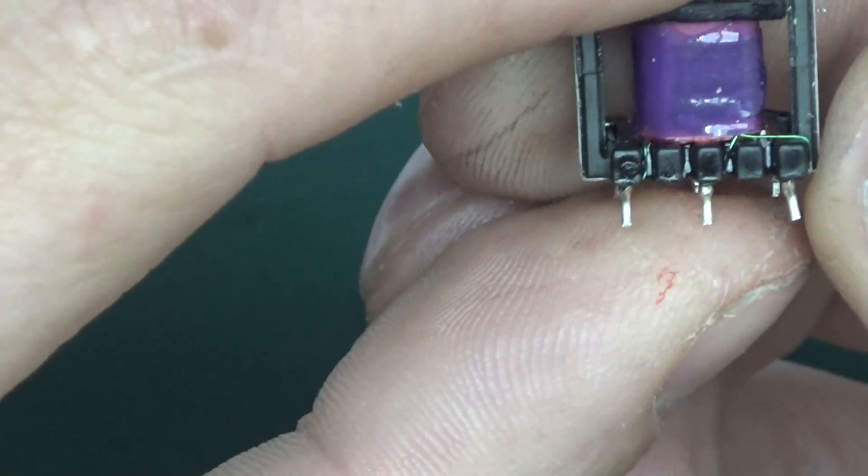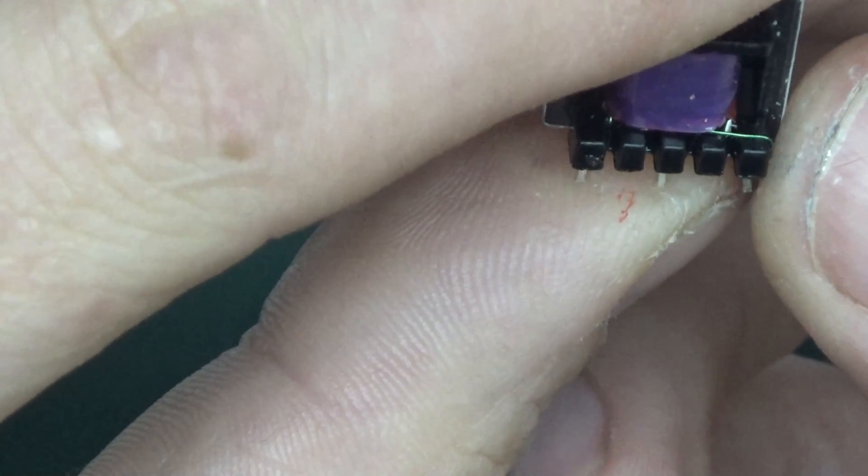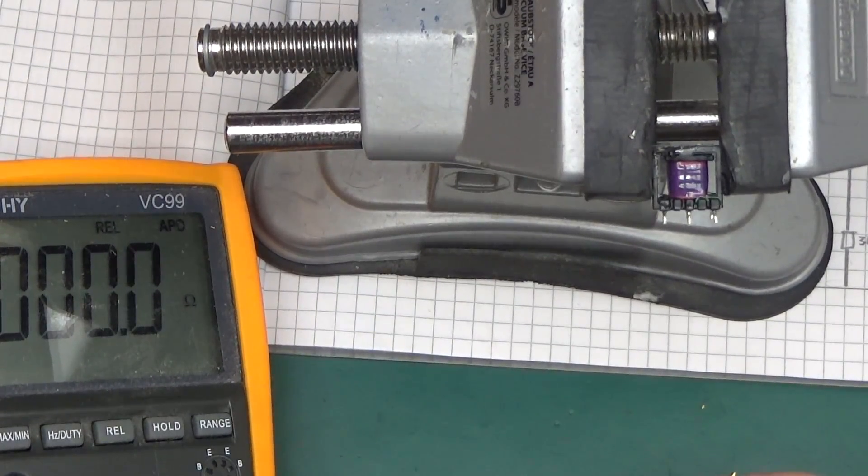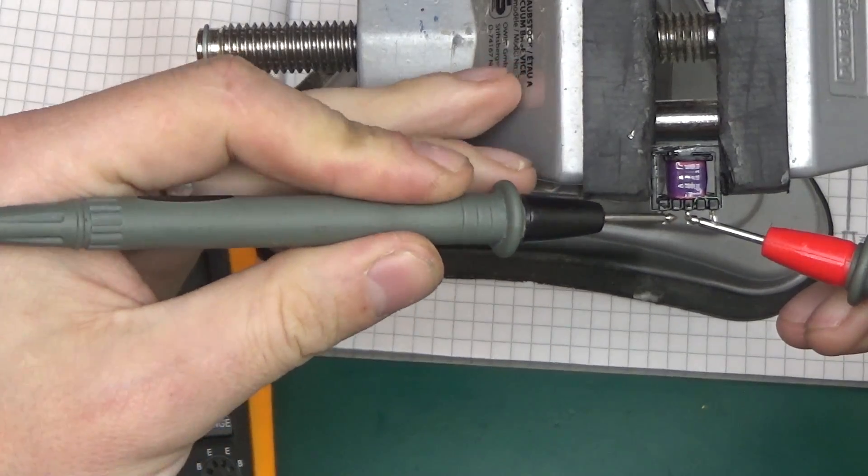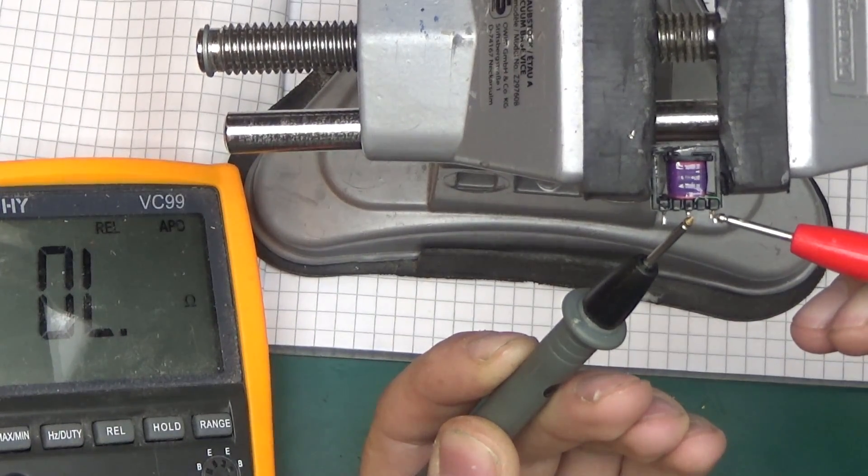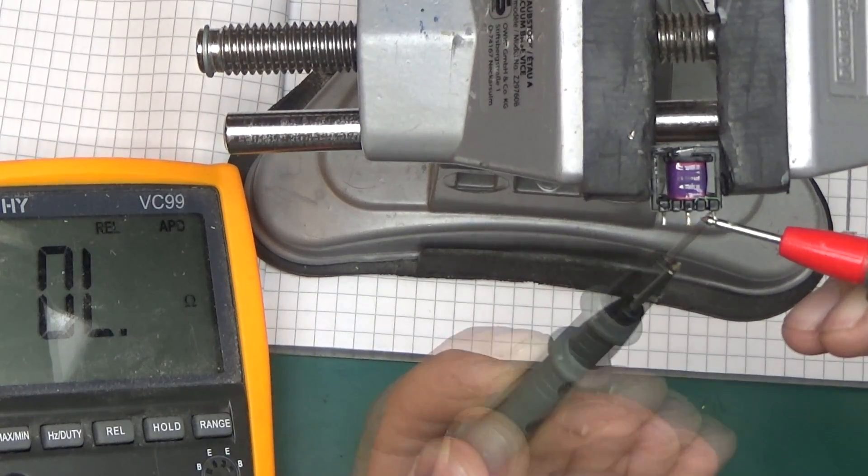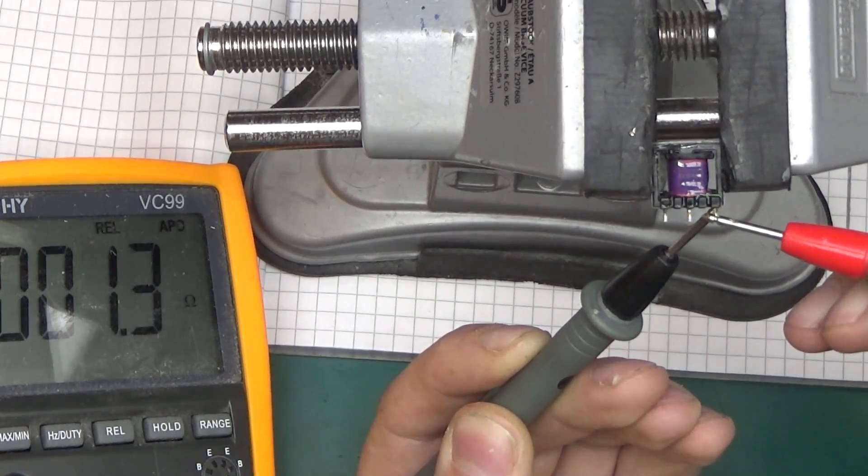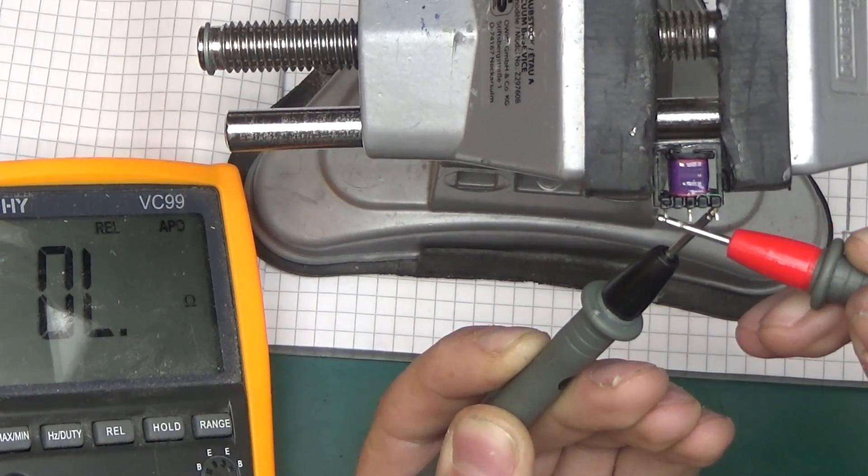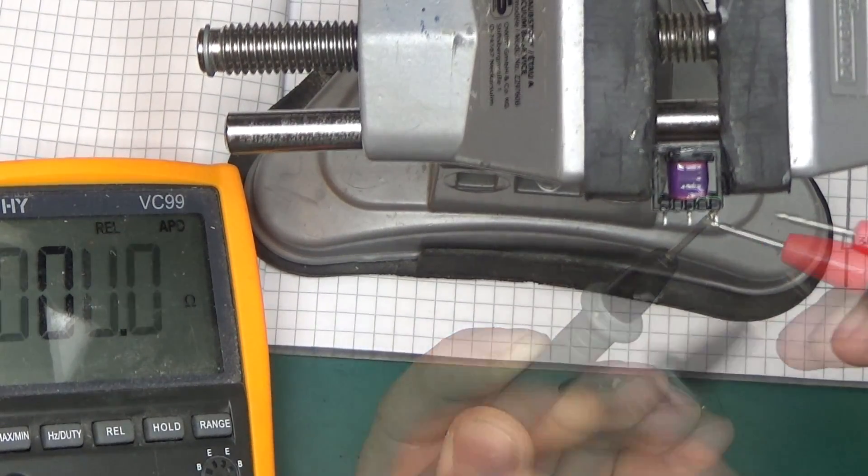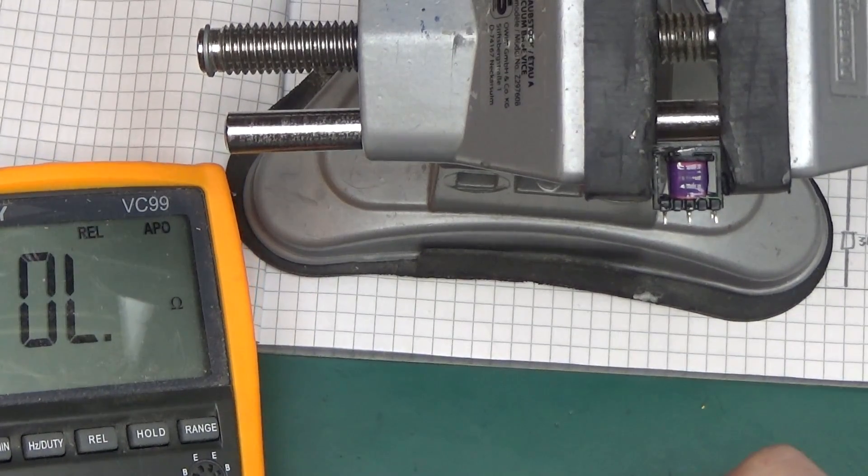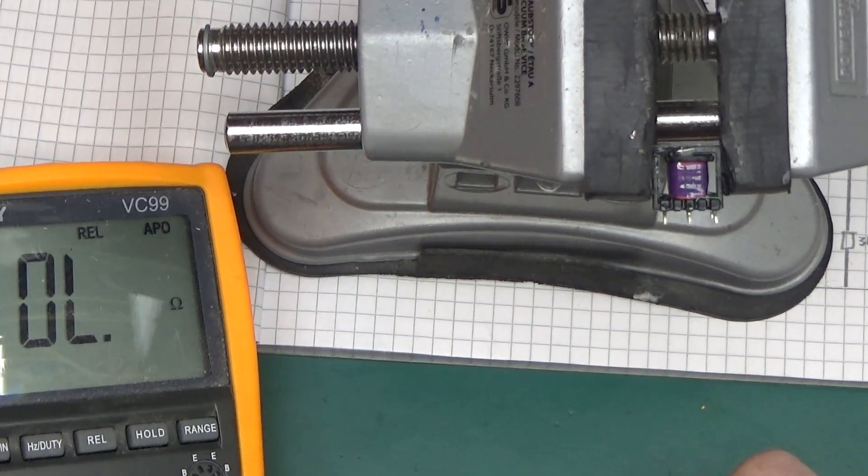Zero out the probes. The first two, 0.6 of an ohm, then the middle one to this one is not connected, and this one and this one is 0.5, 0.6 of an ohm. So those are two separate windings.